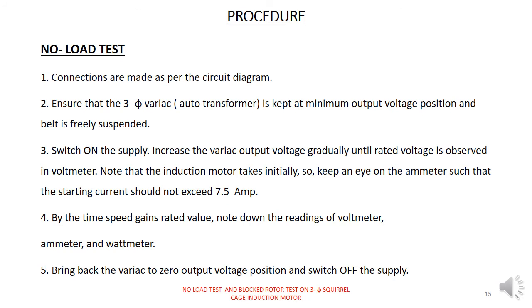Procedure. For the no load test, as usual the connections are made and ensure the variac is kept in minimum position. For the no load test we must use the rated voltage. So by adjusting the variac, keep the voltage at 415 volt and take the corresponding readings of ammeter, wattmeter and voltmeter.